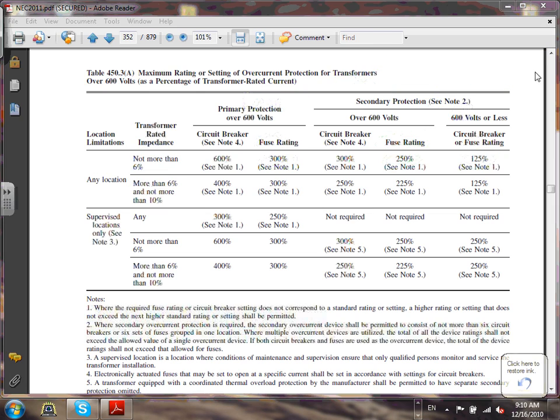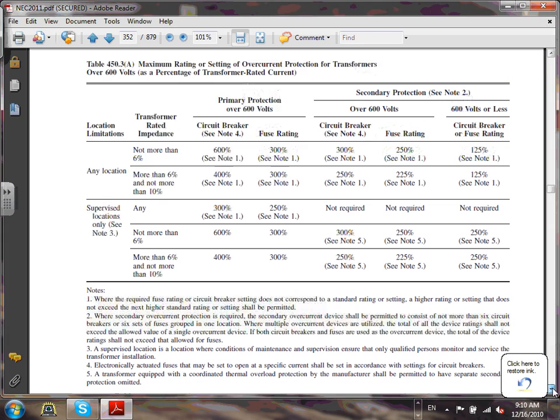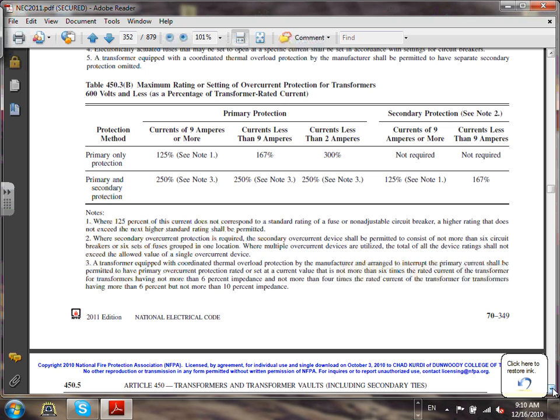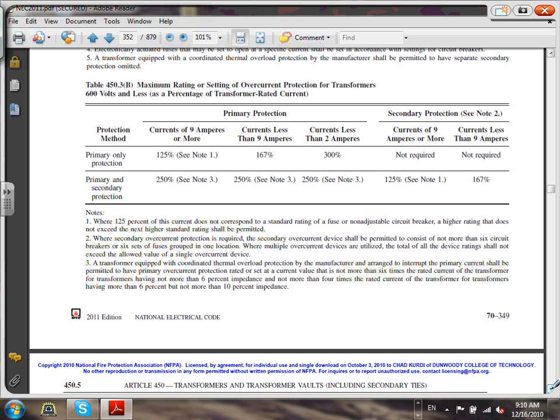Click on that one. I want to go right underneath it, my friends, which is table number 2, which is B. B is very easy. You guys look at B. This is only for voltages 600 volts or less. That's what we most of the time are going to be. Here's my transformer. I have 480 on this side and 208 on this side. So Spencer, my friend, both voltages are what? 600 or less, right? All right.